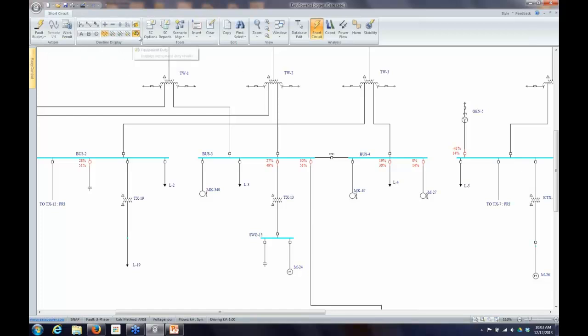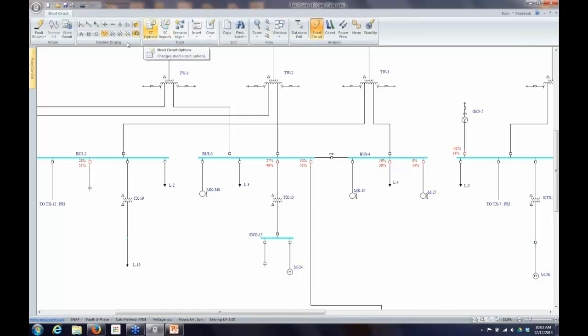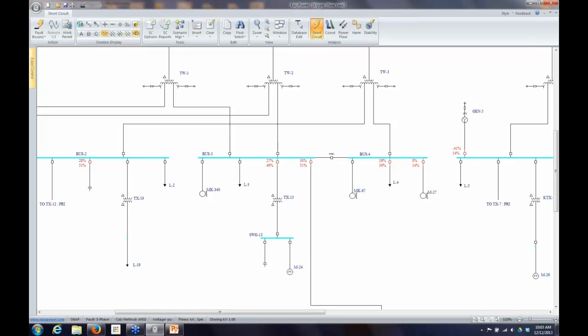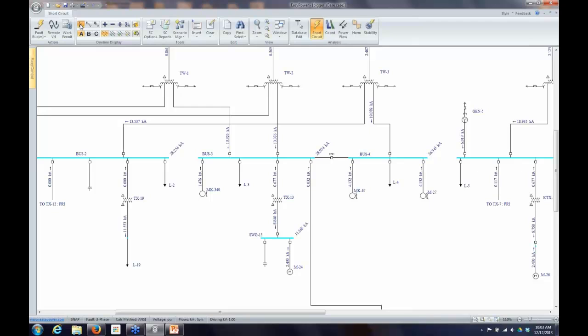I notice I'm in equipment duty report mode, so I'm going to change back to half cycle. When I'm in short circuit, I have short circuit options and my menu changes so I can control what I display on the screen. I'm going to do a half cycle, which is the normal peak short circuit current. Any time I make a change here, it automatically reruns the last calculation.